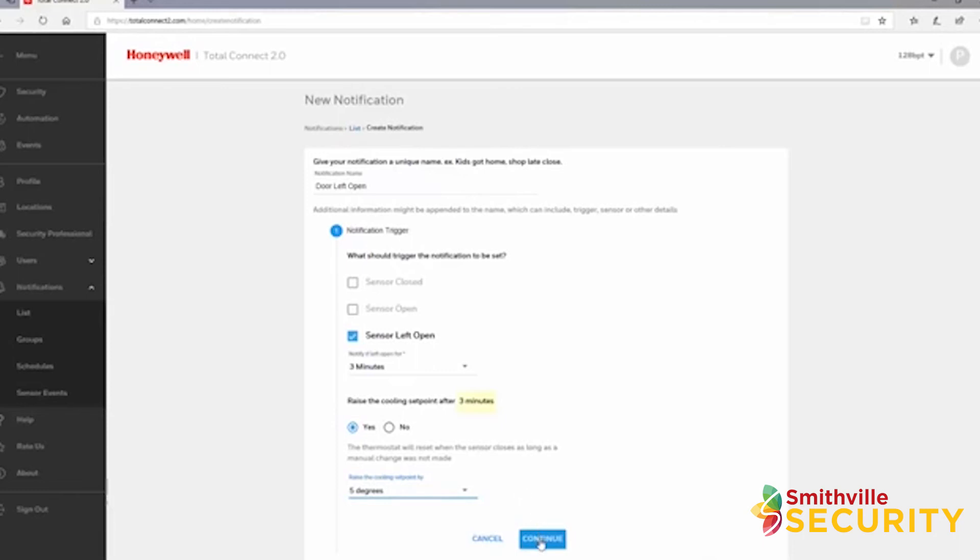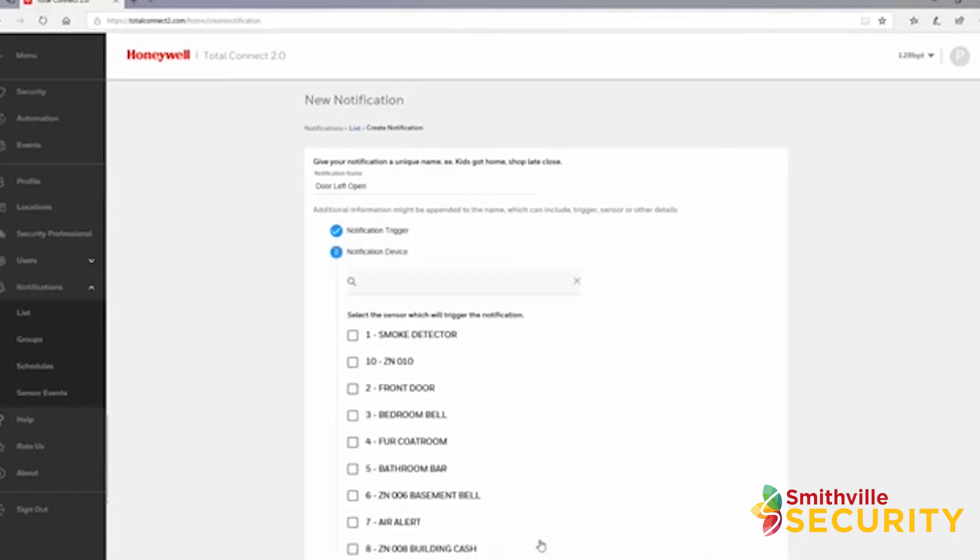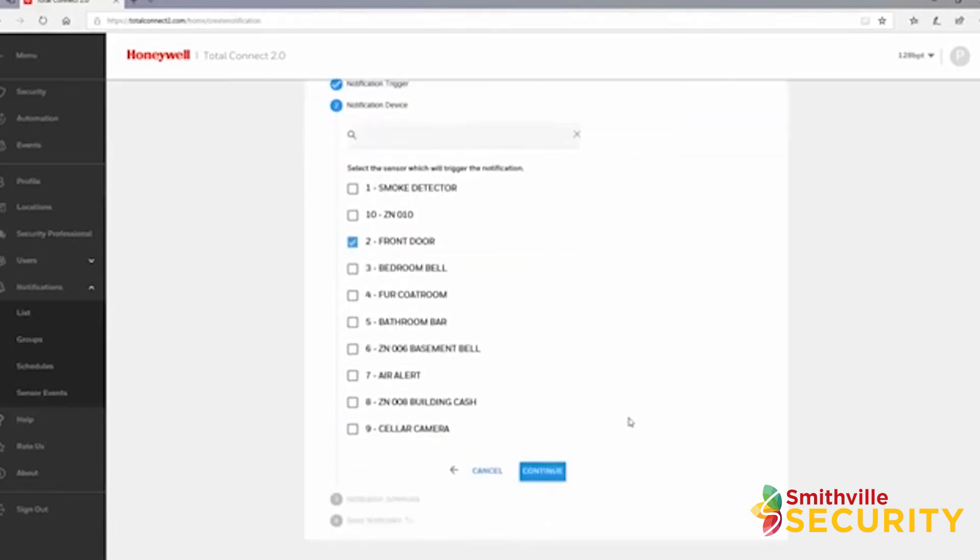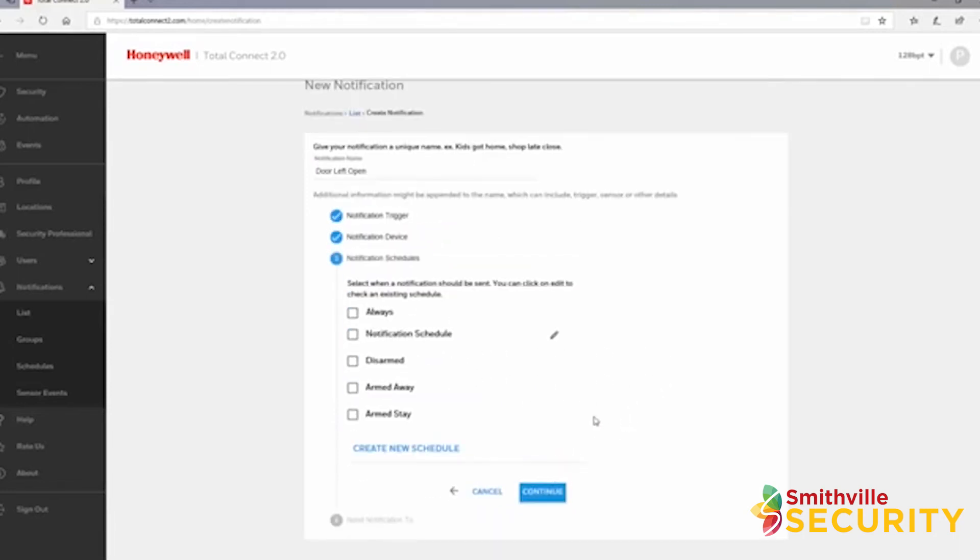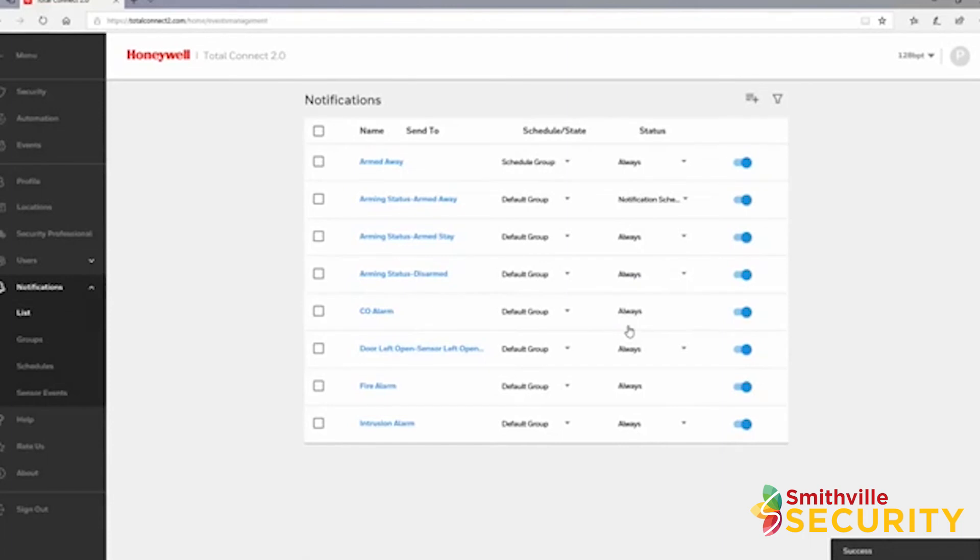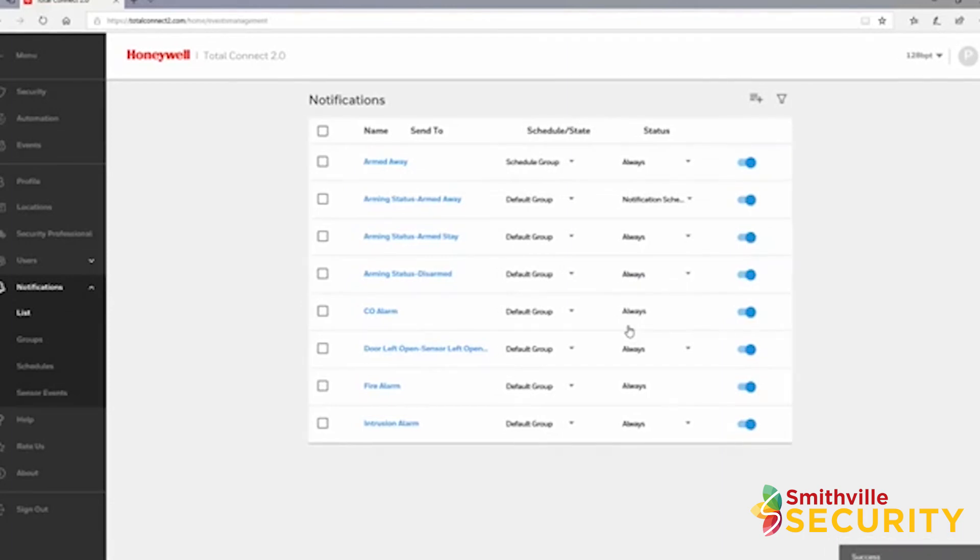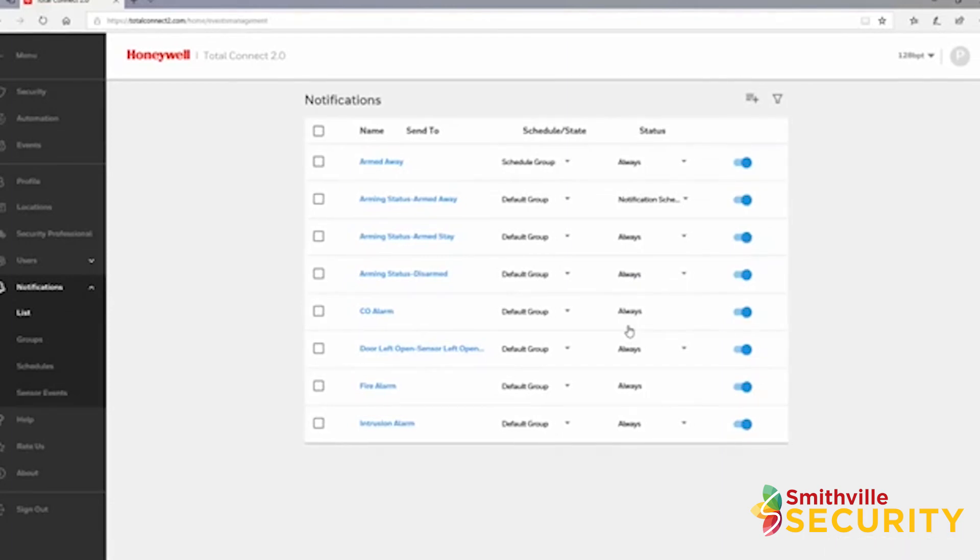Choose which sensor or sensors you want to trigger the notification. As before, select your schedule or panel state and the group. The notification is complete and will send if the front door sensor is left open for more than three minutes, and also adjust the cooling setpoint of your thermostat by five degrees.